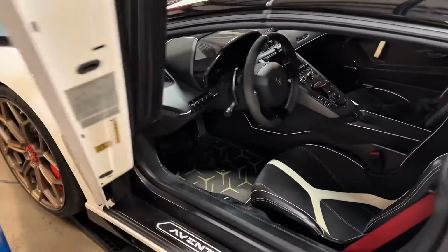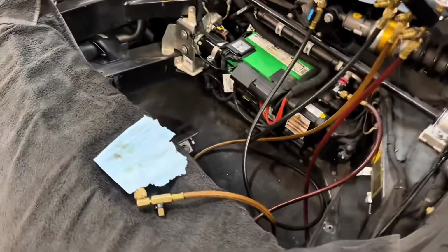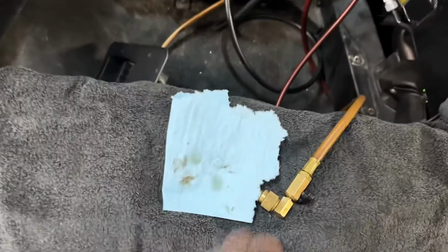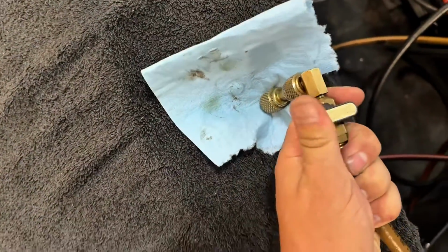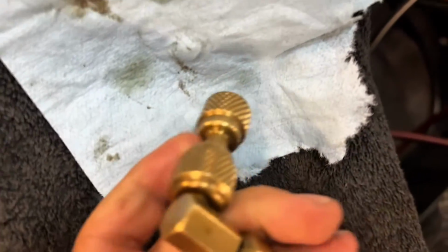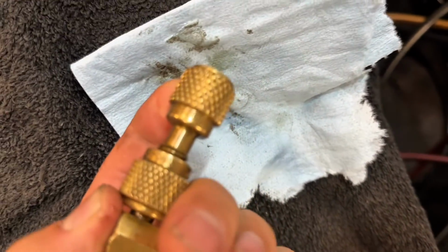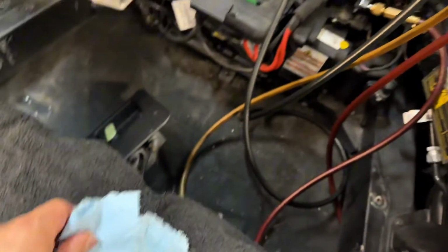Compressor will be needed, and also we'll need to clean out all the lines, replace the expansion valve. There's dirt, it will clog, and from all the debris that was in the line that we just kind of drain it, we get all this black residue right away, and that's from the system.